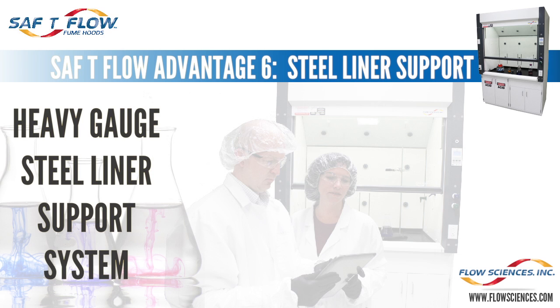Advantage six: the Saf T Flow heavy gauge steel liner support system assures long-lasting and repair-free hood superstructure life and performance. Labs of the 21st century are in constant states of flux. If a hood needs to be moved from one lab to another, the ability to easily move the hood virtually assembled is paramount. Flimsy steel angles and bracket construction can cause the entire superstructure to collapse during disassembly. If you ever wish to change out a lab configuration, lots of labor and replacement parts are needed to move one of these under-built hoods.